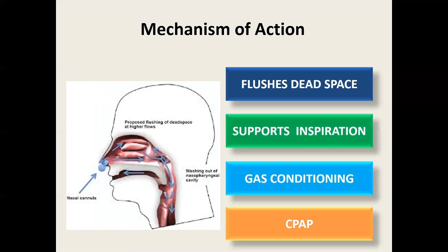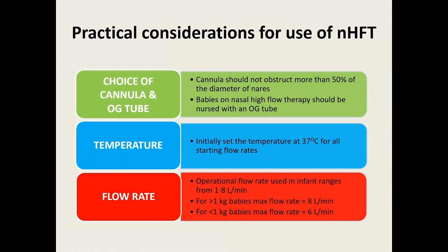It is imperative that the nasal cannula should not obstruct more than 50% of the diameter of the nares, and the temperature of the delivered gas is controlled at 37 degrees centigrade. The flow rates used are a maximum of 6 liters per minute in babies weighing less than 1 kilogram and 8 liters per minute in babies above 1 kilogram.